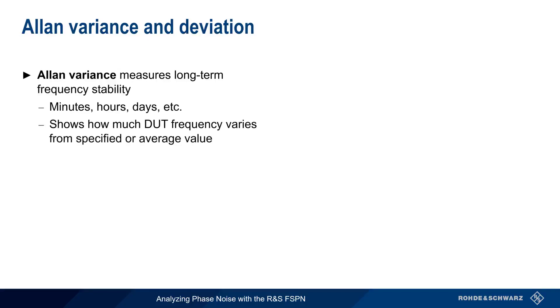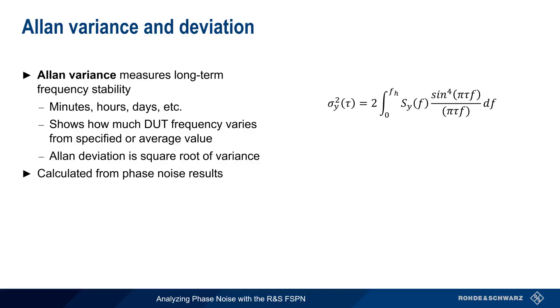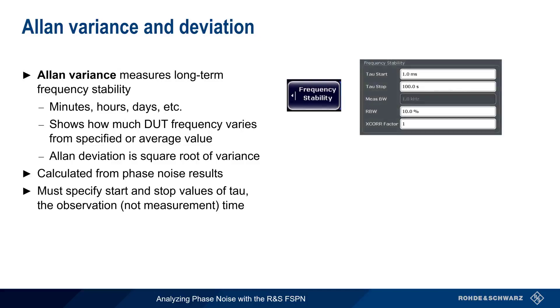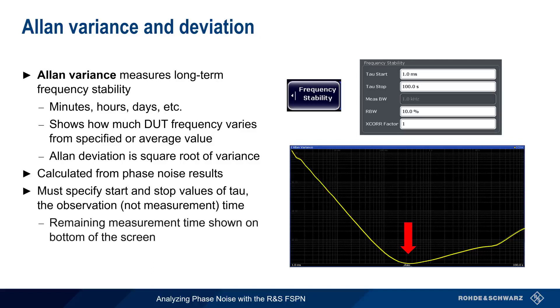The final measurement we'll look at is Allan Variance or Allan Deviation. Unlike phase noise, which is a measure of short-term frequency stability, Allan Variance measures long-term frequency stability, with long-term being on the order of minutes, hours, days, etc. Allan Variance shows how much the DUT frequency varies from the specified or average value. Note that Allan Deviation is simply the square root of Allan Variance. There are many ways to measure Allan Variance, but the FSPN calculates it directly from the phase noise results using a rather complicated formula. Fortunately, the only thing you need to specify for an Allan Variance measurement are the start and stop values of tau, the observation time. The measurement and results are performed automatically. The minimum of the curve is usually the part that we're most interested in. Because of the nature of the measurement, Allan Variance measurements can take a long time to run, so the remaining time indicator at the bottom of the screen may be helpful.